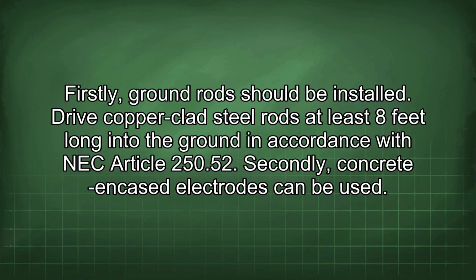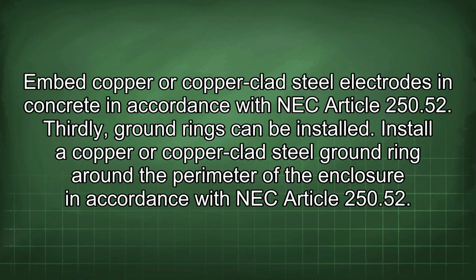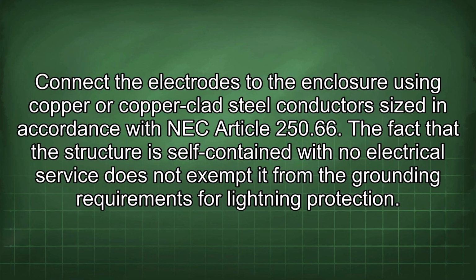Secondly, concrete encased electrodes can be used. Embed copper or copper-clad steel electrodes in concrete in accordance with NEC Article 250.52. Thirdly, ground rings can be installed. Install a copper or copper-clad steel ground ring around the perimeter of the enclosure in accordance with NEC Article 250.52. Connect the electrodes to the enclosure using copper or copper-clad steel conductors sized in accordance with NEC Article 250.66.